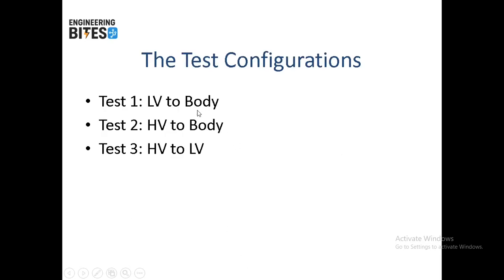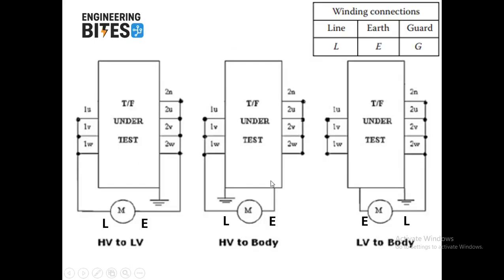We have 3 types of tests. The first one, the low voltage to the body. Test 2, high voltage to the body. Test 3, high voltage to the low voltage. We can see in this diagram the 3 types of testing. We have the megohmmeter device. It has 3 points. We will use the line and earth points.